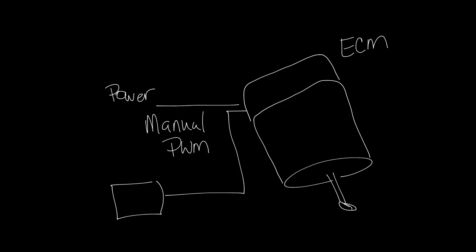ECMs take AC power and internally rectify it to DC voltage. The integral controller for an ECM is designed to accept a pulse width modulated, or PWM, speed control signal. This type of control is far superior to a PSC motor with an SCR controller in terms of energy and efficiency. Since there's no distortion of the motor power, there's no excess heat to be dissipated, and no motor hum at reduced speeds. ECMs run cool to the touch.